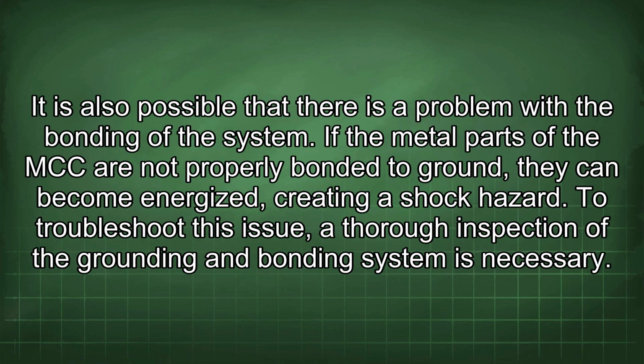It is also possible that there is a problem with the bonding of the system. If the metal parts of the MCC are not properly bonded to ground, they can become energized, creating a shock hazard. To troubleshoot this issue, a thorough inspection of the grounding and bonding system is necessary.